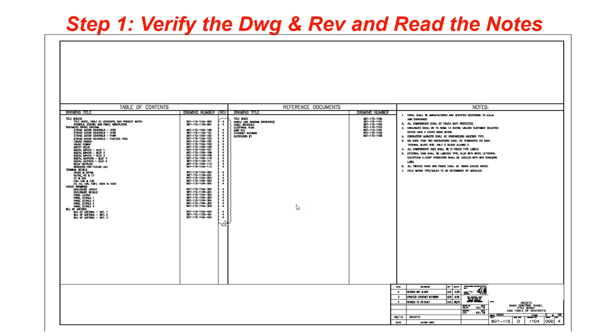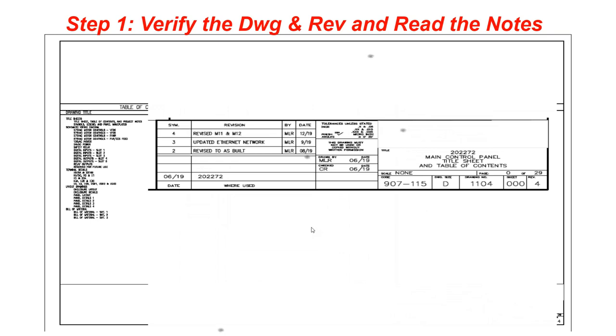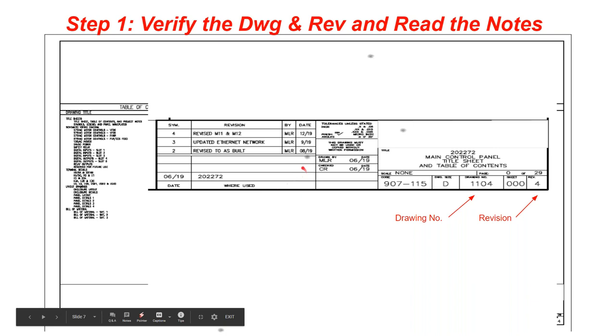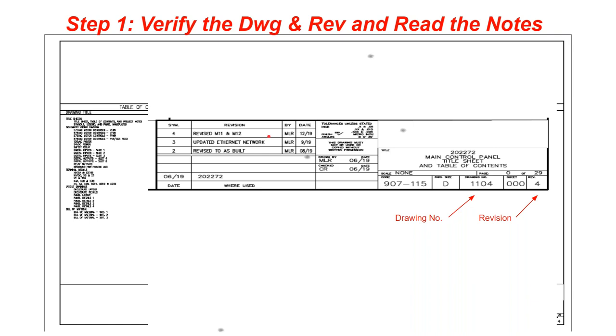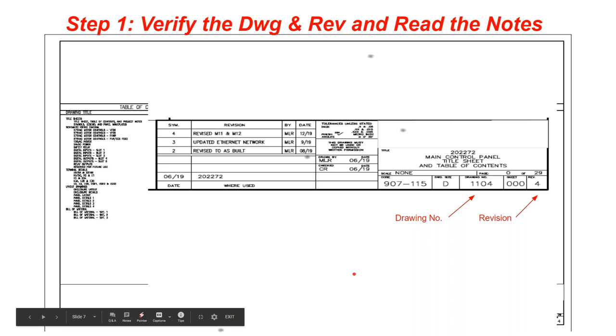The first thing to do when looking at a drawing set is check the title block — make sure you have the correct drawing number and, just as importantly, the correct revision. You can see there were revisions made as-built, such as adding an Ethernet network and later revisions, all dated. The purpose of the title block is to make sure you have the correct drawing set and revision.